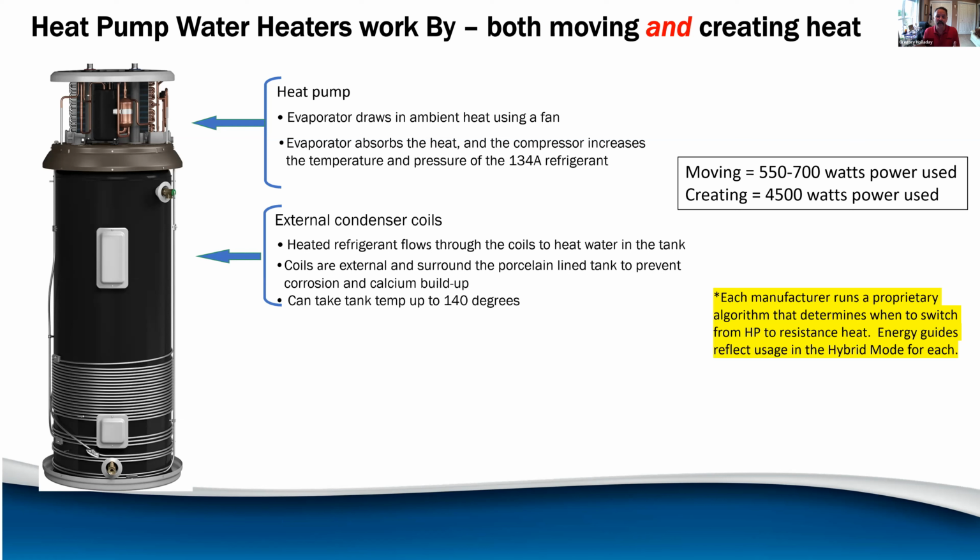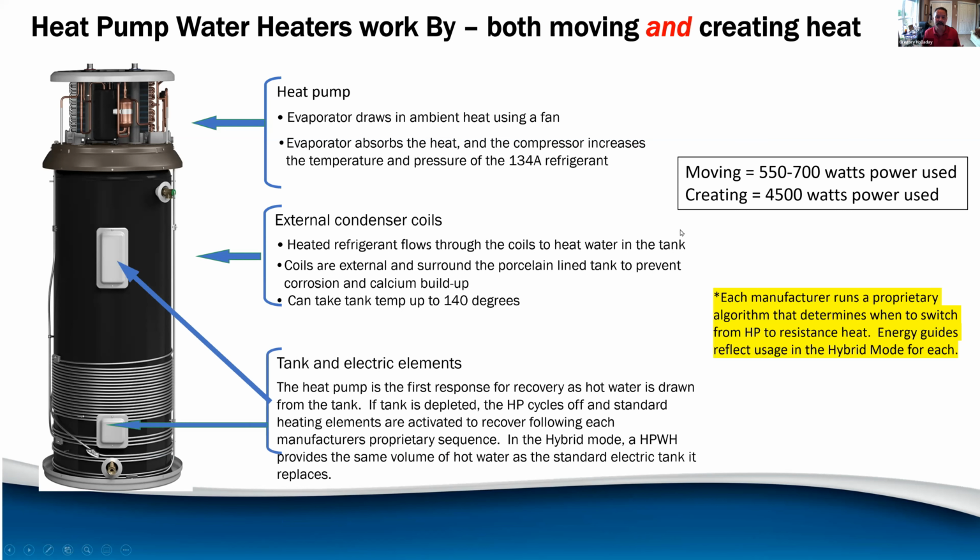Because if we don't touch the water, we don't have to descale anything. So it's pressed into the side of the tank. It's then covered with about 2 inches of non-CFC high density foam, which creates an R19 energy blanket. And this water heater that you're seeing here only loses about 5 degrees in 10 hours. So that means it doesn't run essentially when you're not at home. Now, it has backup heating elements in it because most every house has a 13-year-old that says, my job in life, I swear to God, every day is to use every drop of hot water there is whenever I jump in the shower. So the water heater says, I'm going to primarily use the heat pump.